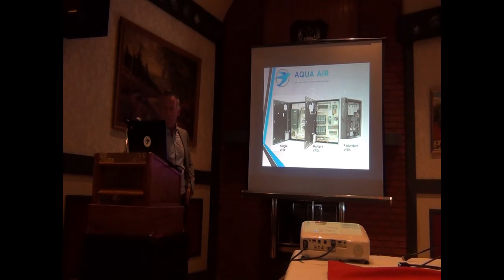When we talk about fan walls and VFDs, we have a little bit different of a scenario. There's more options for controlling the fans because you have more fans. Let's say we had 10 fans in a fan wall application. You can have one single VFD controlling all 10 fans. There'll be smaller motors and all that, but it'll adjust all 10 fans to meet the load. You can have multiple VFDs. So if you had 10 fans, you could have 2 VFDs, each running 5, or 5 VFDs, each running 2, whatever scenario you think would work.